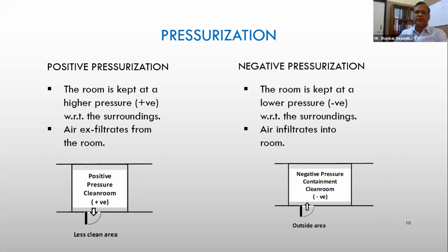The other case is a negative pressurization, where we don't want the contaminants from the room to go to the other parts of the hospital. Very much the case like we have in the scenario of COVID these days. These rooms are at a lower pressure with respect to the surroundings, and the air infiltrates into the room. Here, the exhaust air volume will be larger than the supply air volume. There will be an exhaust separately provided so that the negative pressure is taken care of.